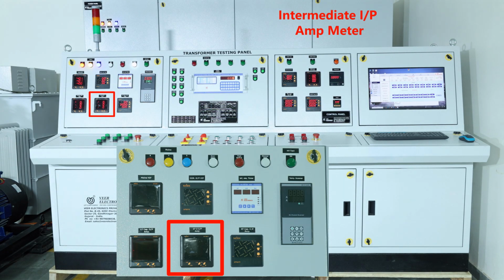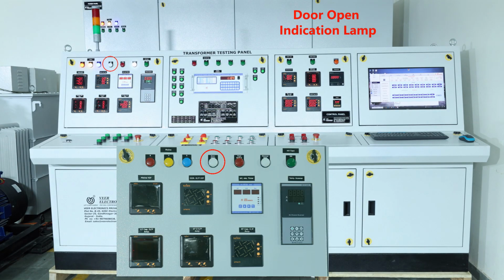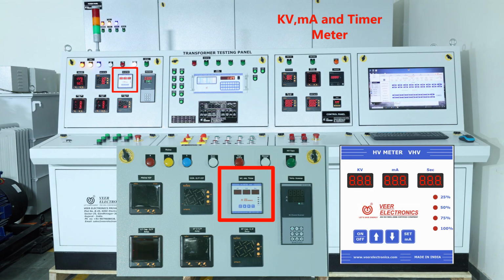This is the door open indication lamp. It shows the test job area door open condition. This is the foot switch indication lamp for open condition. This is the combined kV, milliampere and timer meter for HV test. Here it shows the high voltage transformer output voltage in kV, leakage current in milliampere and time in seconds.